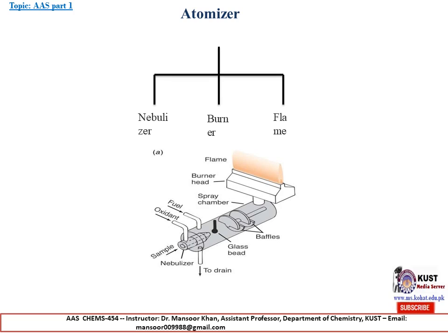It consists of the nebulizer, oxidant, drain, fuel, glass beads, baffles, spray chamber, burner head, and flame. These are the various portions of the atomizer. The application of the atomizer is to convert the element of interest into its neutral gaseous atomic form.